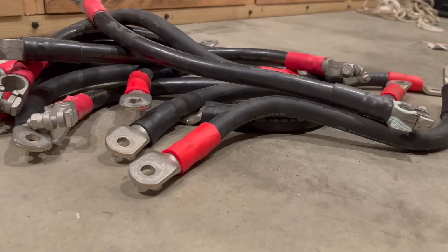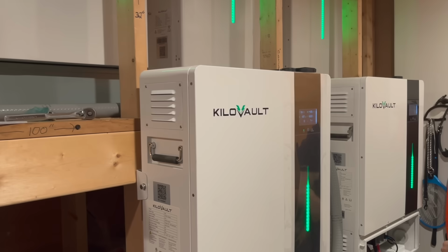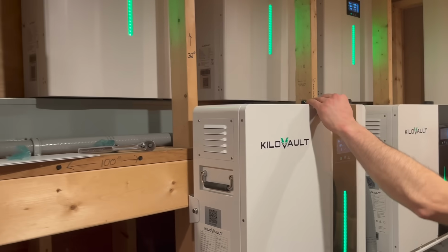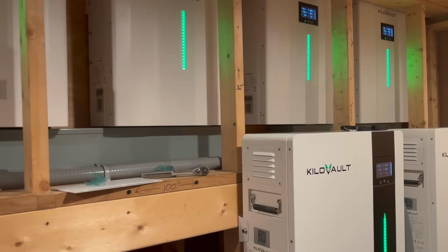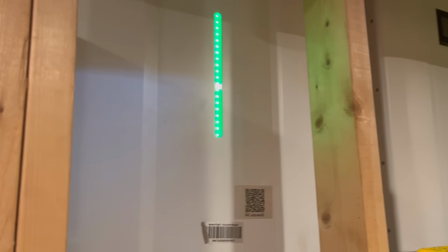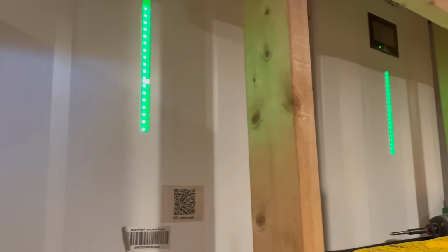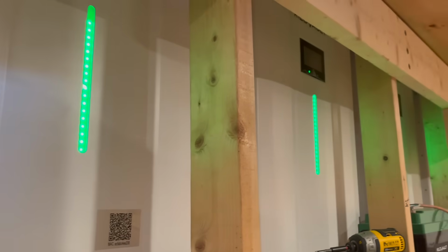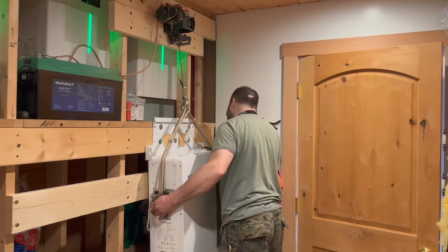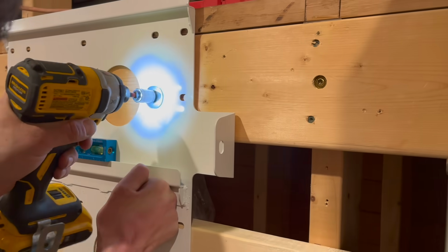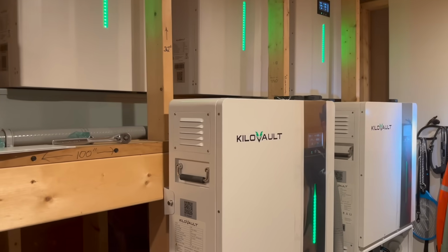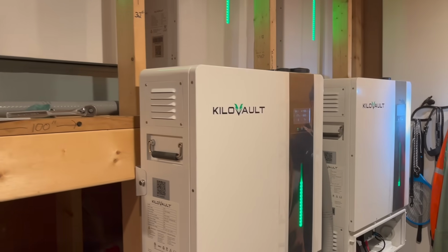The system was first installed with an AGM bank, but that has since been upgraded to the KiloVault HAB lithium iron phosphate batteries. The initial bank consisted of four V2 HAB batteries for a total of 30 kilowatt hours, but was expanded to 45 kilowatt hours total by adding two additional V4 HABs a year or so later.